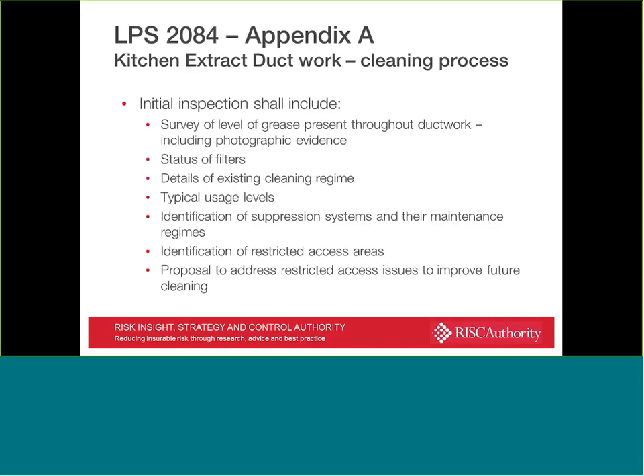Two particular sections to draw your attention to, one that deals specifically with the cleaning process, and you can see there the criteria. Initial inspection requires a survey of the level of grease, including photographic evidence to be taken, a review of the status of the filters, details of the existing cleaning regime, details of typical usage levels, identification of suppression systems and their maintenance, restricted access areas, and then some proposals to address restricted access issues to improve future cleaning.